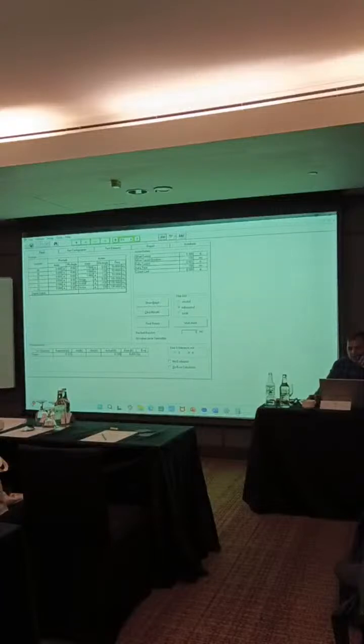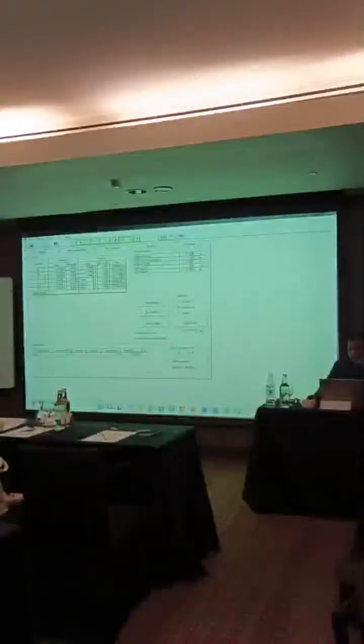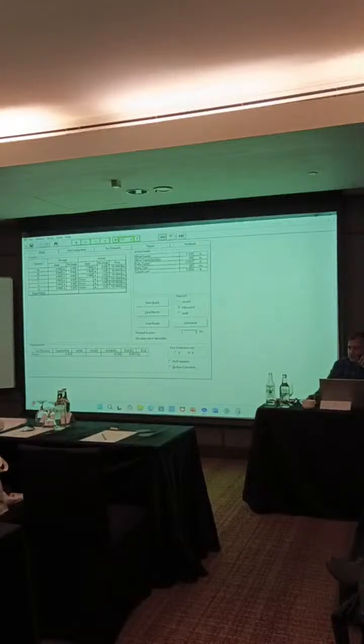So what is happening, it is starting from 0.3 ampere and it is reducing in 0.001 step. So when relay will trip, that trip current will be recorded here. So we come to know what is the second harmonic current, till what current it is blocking. So that is what we require.